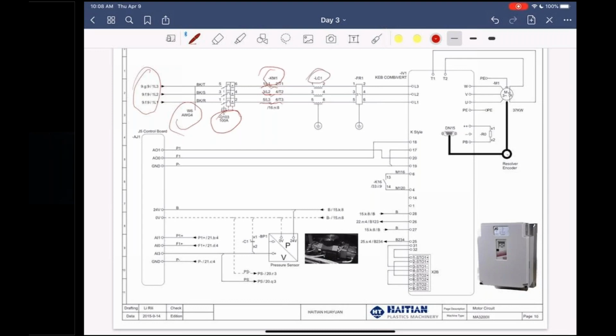It then goes to this LC1, which is your line filter, and your FR1, which is your other filter, and that feeds line 1, line 2, line 3 into the KEB drive. The KEB drive has a couple other options. It has this T1, T2, which is a thermistor. This thermistor keeps track of the temperature of the motor itself.